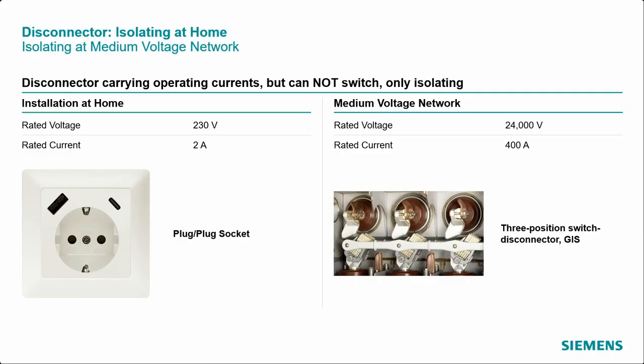A disconnector can't break any kind of load and has no fault protection. It is used to safely isolate sections during maintenance or upgrade, or to disconnect a segment of a distribution system for an inspection or a repair.